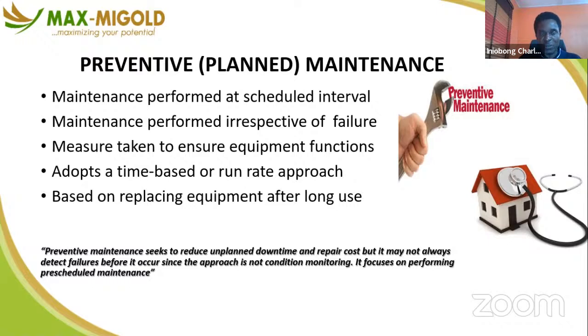For outsourced services, maybe you outsource your generator to a vendor to service, and the agreement is that the vendor needs to come every 2 months to service your generator. It means that whether the equipment is still okay or not, because of that agreement, the vendor will come and still carry out maintenance. I've seen situations where you look at the oil, the viscosity is still good, you look at the parts, the belt, everything is still good, but because there's an agreement that we need to service every 2 months, you need to do that. You must stick with the agreement. So maintenance is performed irrespective of failure.